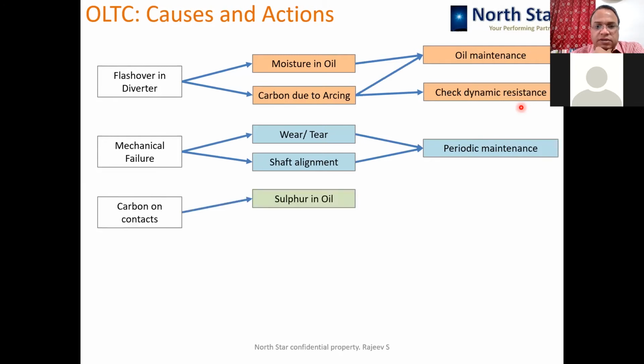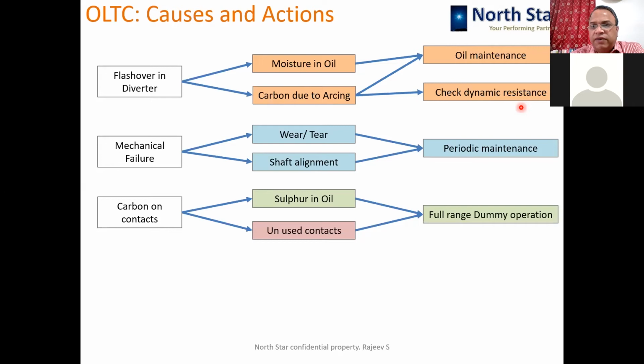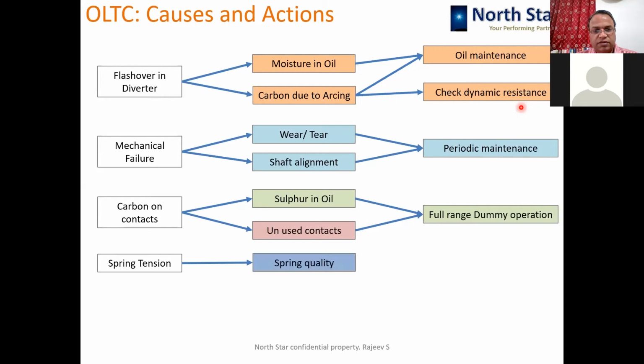Then you will find carbon on the contacts. There is pyrolytic carbon on the contacts because of sulfur in the oil, and that is normally found on the unused contacts. So it is advisable, as a preventive maintenance activity, that the OLTC should be operated over the full range in a dummy situation, so that the carbon deposit gets wiped off. This carbon deposit can cause excessive arcing. That's why it has to be cleaned off. Then spring tension gets affected, so spring quality could be an issue, and you can replace and correct it. So the OLTC is something which requires to be maintained quite often, and the OLTC supplier decides the maintenance frequency based on the number of operations or number of cycles. So that is to be respected.